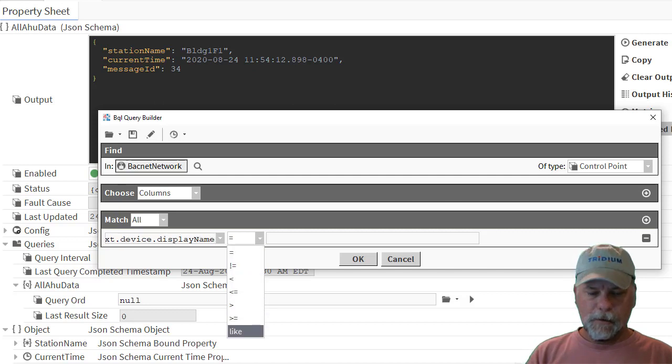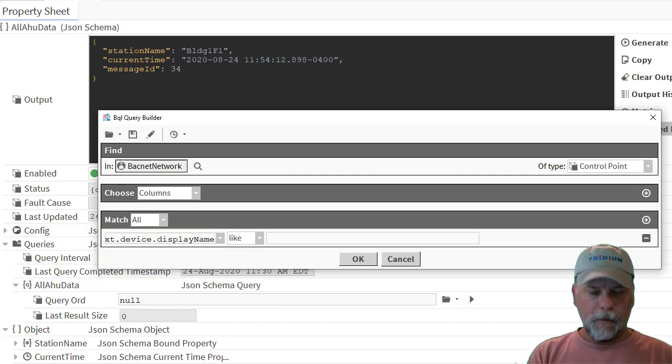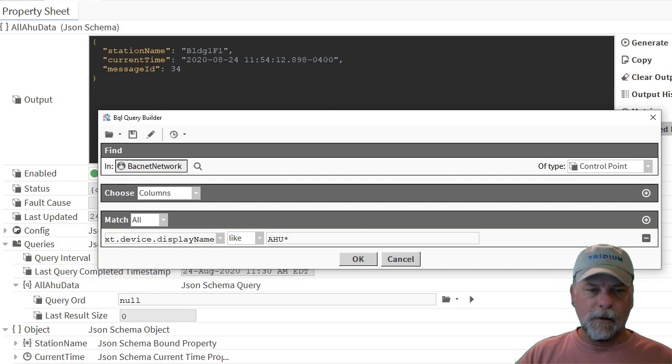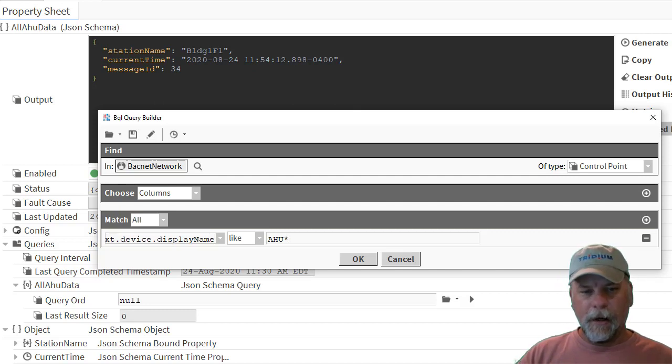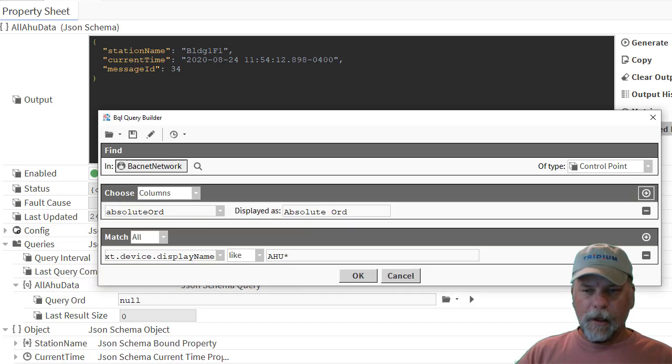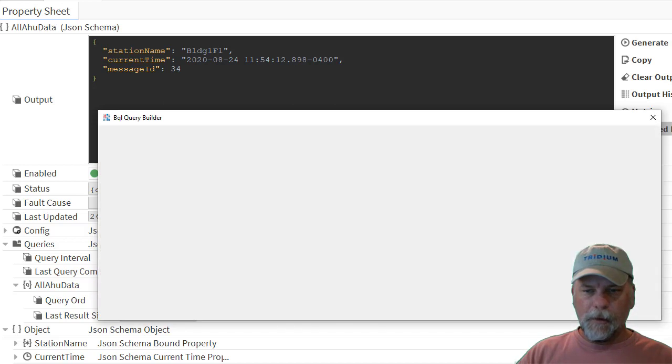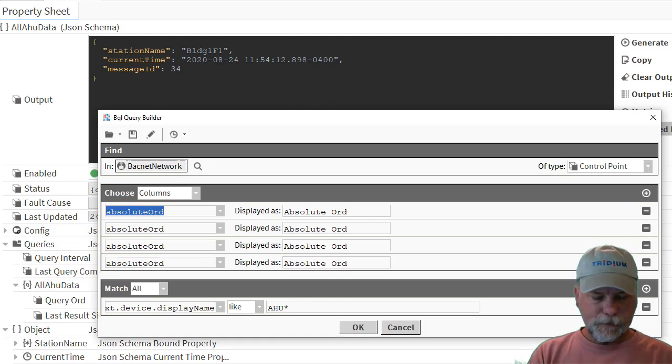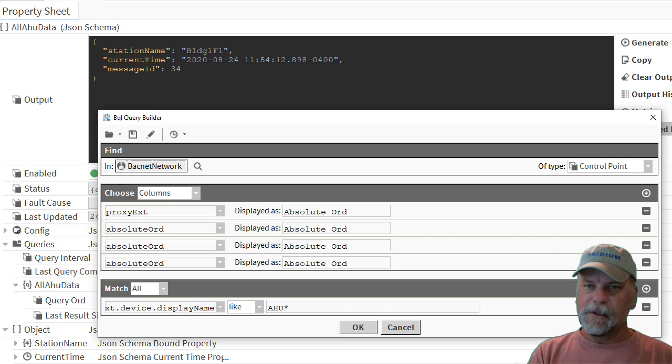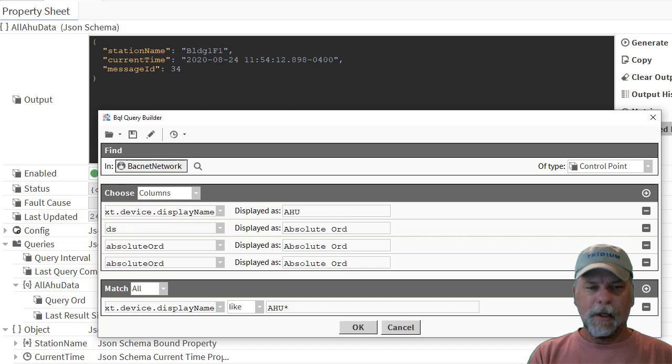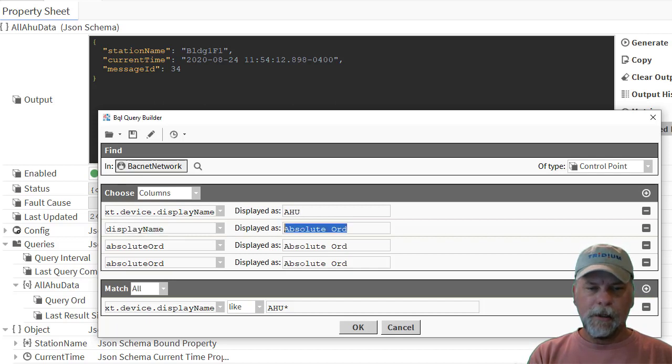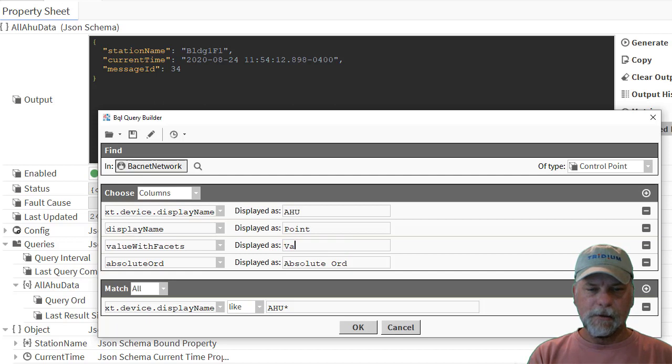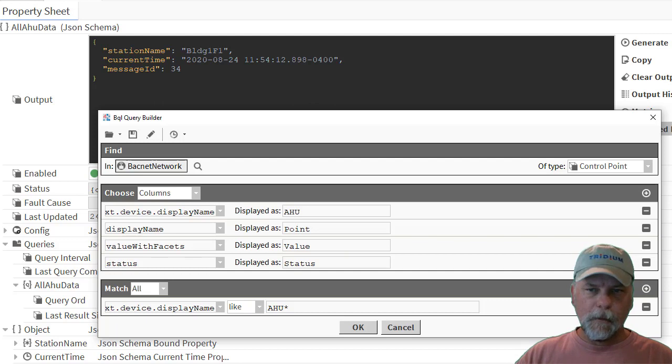And we can check for that being like AHU something. So that'll find all the driver proxy points under the BACnet network that are under air handler devices or devices at least whose names start with AHU something. And then we can specify a projection of what we want to see. Maybe something like proxy XT dot device dot display name as AHU. Display name, which will be the display name of the point as a point. We can do value with facets as value. And then maybe status as status.